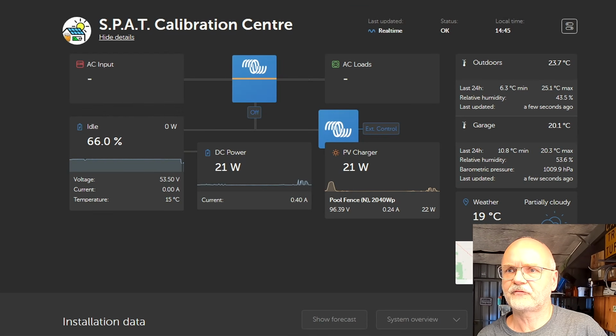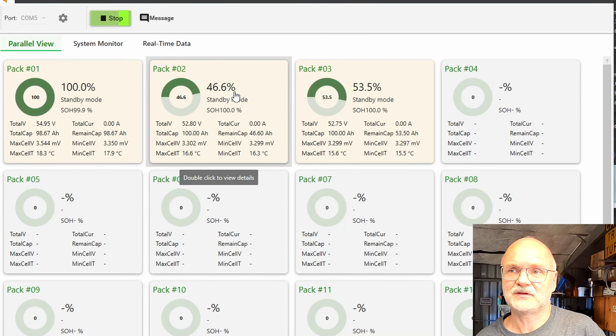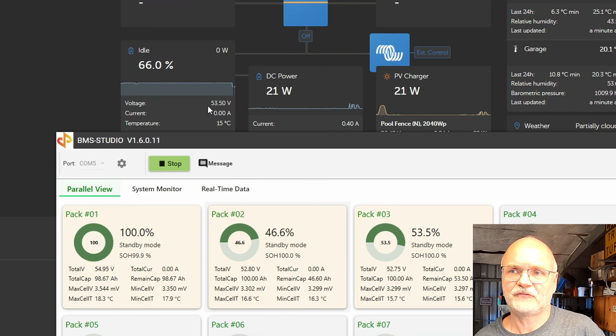Before we conclude this video, I want to show you the result of having 3 batteries in parallel with a communication setup, in this S.P.A.T. calibration centre here in the Victron VRM. You can see we've got a state of charge of 66% now, and it actually averages these 3 states of charge. We also have a system voltage of 53.5 volts, again averaging all 3 individual battery voltages. If the master battery takes 50 amps and the other 2 only 10 amps, it will show us 70 amps here as the current. The temperature, I'm not sure if this is an average as well. What do we have here? Could be an average as well.